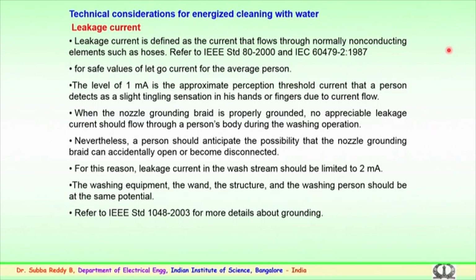So, these details are further very clearly explained with reference to the IEEE standard 1048 about the grounding of the hose pipes, the currents to be contained and how it is to be done. So, further information is available. You can read the standard for more details about the grounding aspects, particularly for the nozzles and the hose which is being used for the cleaning operations.